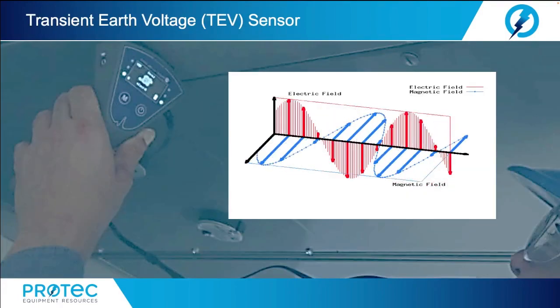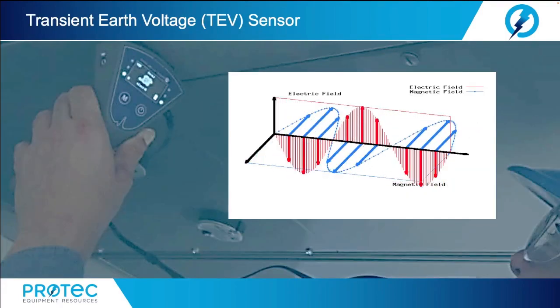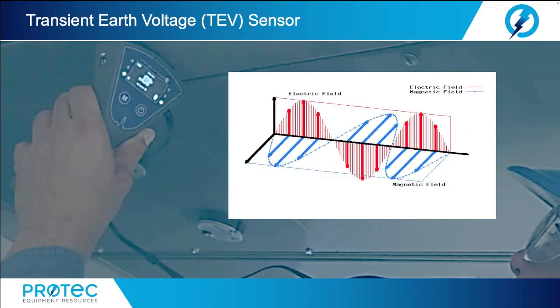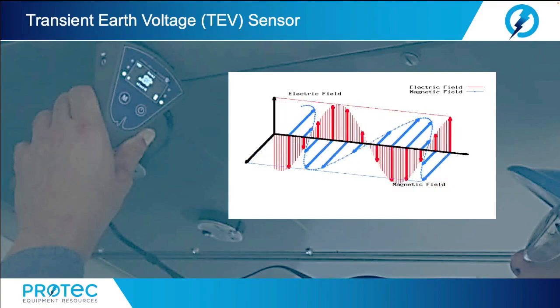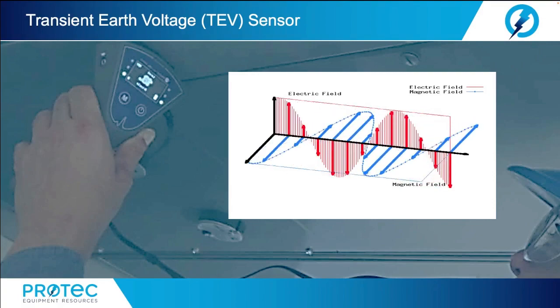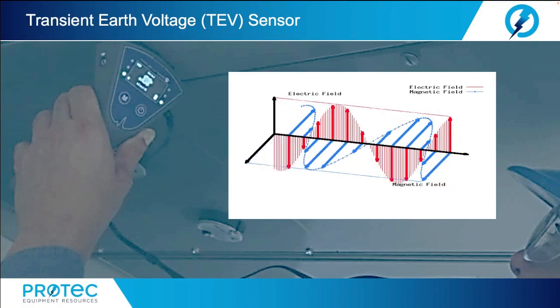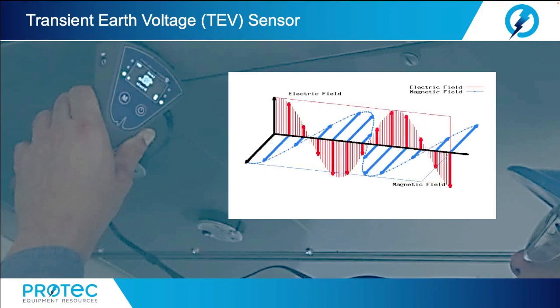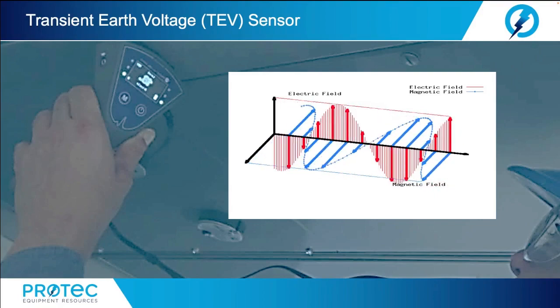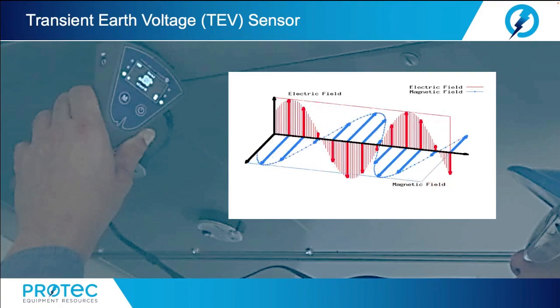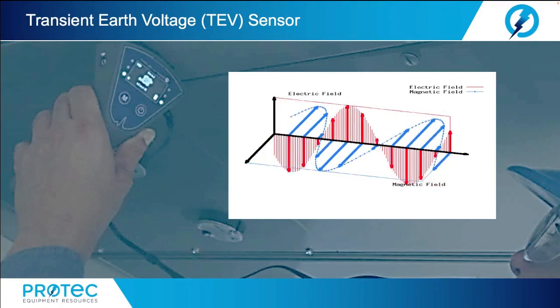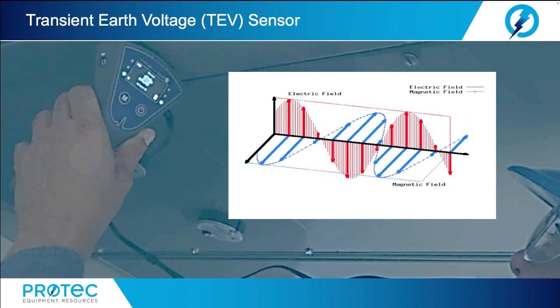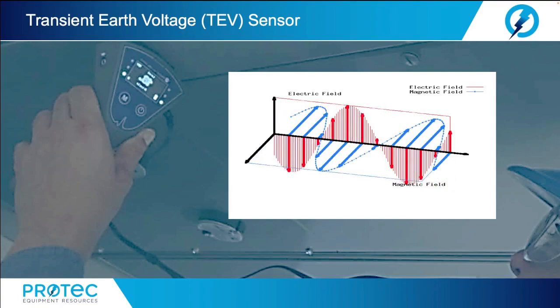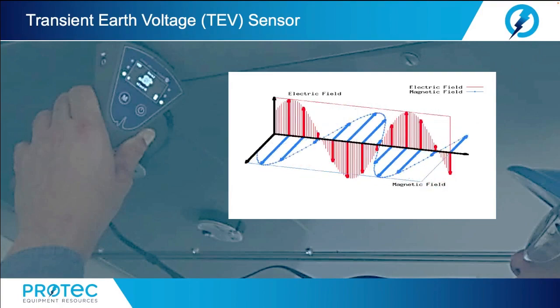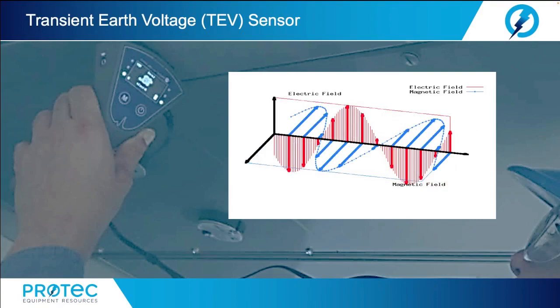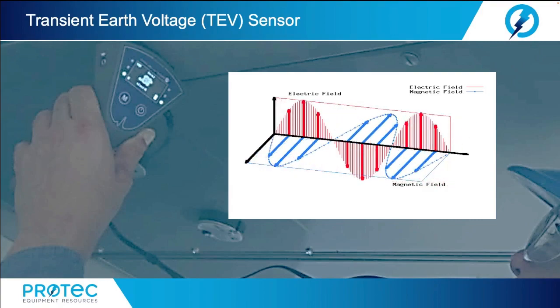All right, the next thing we're going to talk about is the transient earth voltage, or TEV. Now, partial discharges in medium voltage power equipment will produce induced radio frequency signals, which are sustained and can be detected at the surface of medium voltage enclosures, such as metal-clad switchgear, manholes, and metal enclosures. TEV signals spread out quickly on the ground plane. For this reason, it is very difficult to locate the origin of a TEV signal.